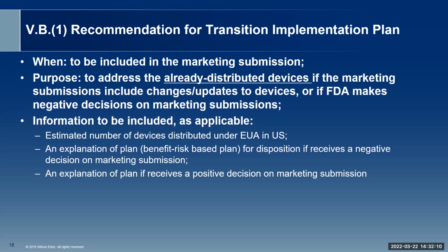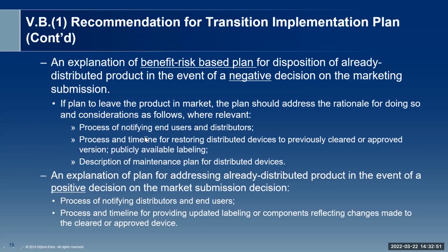The information you should include in the transition implementation plan: again, you need to give the FDA an estimated number of devices, how many devices you have already distributed in the market, and an explanation of a benefit-risk-based plan for disposition of your products if you receive a negative decision from the FDA on your marketing submission, as well as an explanation of your plan if you receive a positive decision on your marketing submission. In the next slide, I'll give you more details about these two plans that you need to include in your marketing submission.